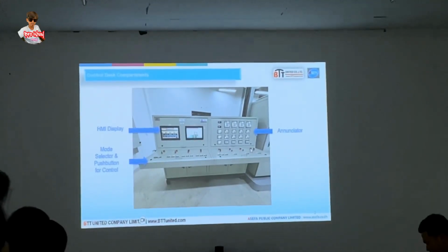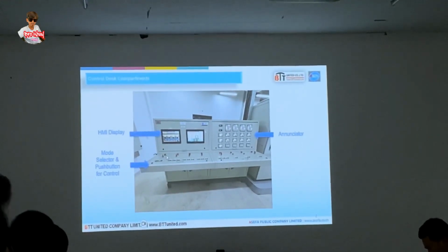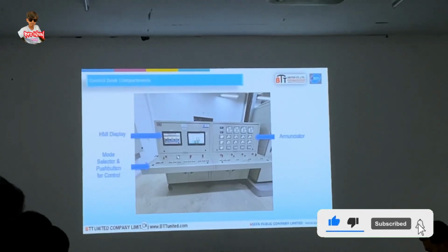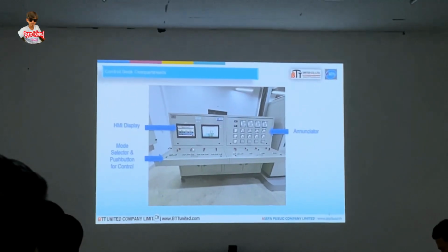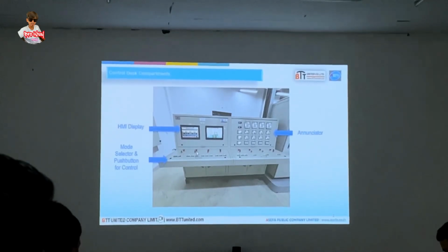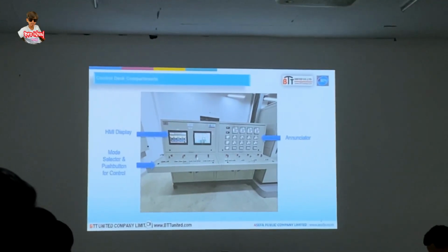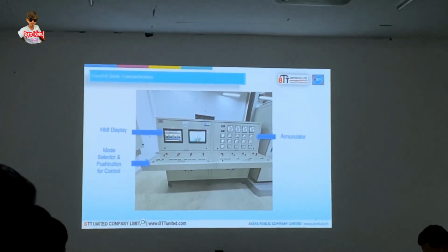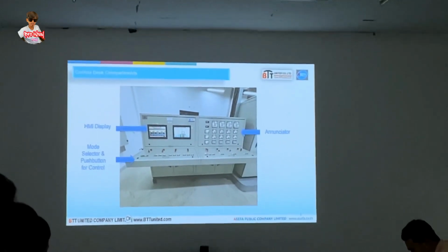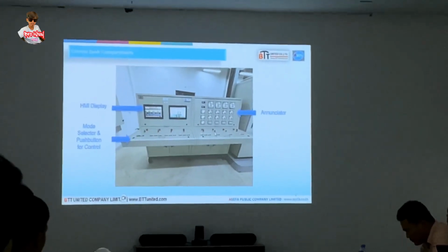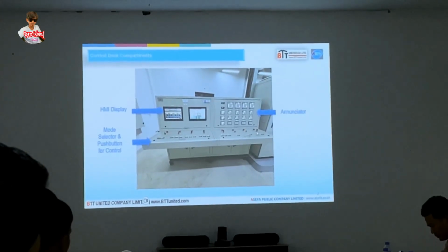In case of an emergency, once you push this emergency stop, the whole system that belongs to this particular line will shut down. So this is for main pump number one. This whole system for main pump number one will shut down if you ever press this button right here. Same goes for pump number two right here, pump number three with the red button, pump number four with the red button, and then you have those three submersible pumps. Number one, number two, and number three right here.